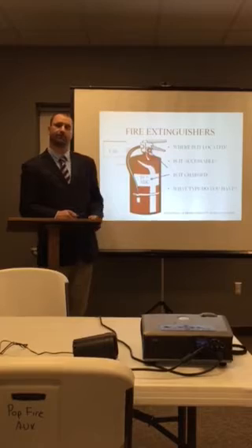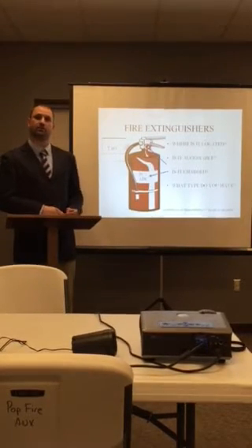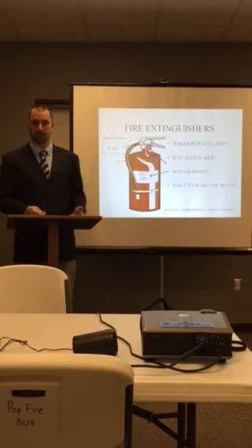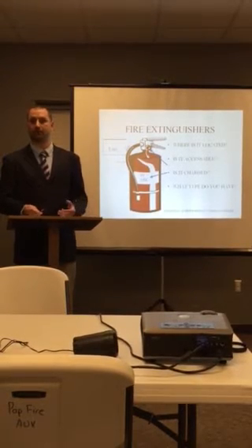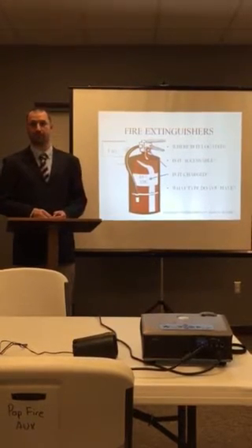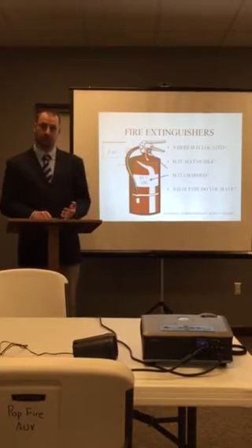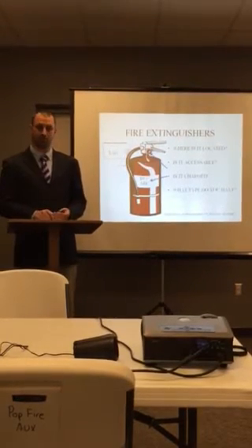And what type do you have? The type of extinguisher is based off of the fire you're going to use it to put out, such as Class A, B, C, or D. The majority of your fire extinguishers out there are A, B, C, meaning that they can be used on your combustible materials, your flammable liquids, and your energized electrical equipment.